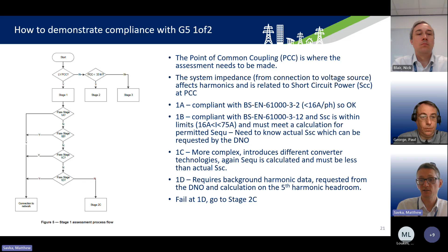So just briefly talking about stage 2C. To do this, the customer needs to obtain the background harmonics, obtain the system fault level or the short circuit power, and then follow the steps in G5 to verify each imposed voltage harmonic is within the planning limit, and also that the total harmonic voltage distortion is within the planning limit. And normally we'd expect that to be delivered in the form of a report, which would come to us to review.